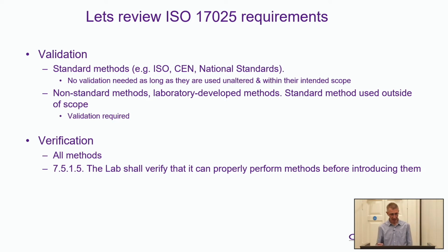If you're using non-standard methods, laboratory developed methods, or standard methods outside of their scope, then validation is required. Verification, it says, is required for all methods. And it says there in 7.5.1.5 of 17025, the lab shall verify that it can properly perform methods before introducing them.